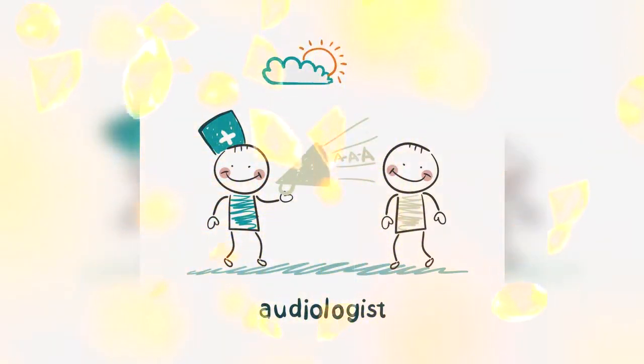The cochlear implant device is comprised of internal and external pieces. The external part consists of a microphone, battery, magnet, radio frequency antenna that transmits sound, and a microcomputer that processes sound. The microcomputer converts sounds into signals, sending the sounds to the implanted internal part which receives the sounds. The internal part, the receiver, is called a receiver/stimulator and includes a microcomputer, radio antenna, magnet and electrode array. The magnets are of opposite polarity and hold the external device over the internal device. The radio frequency antennas allow digital communication between the external and internal parts.